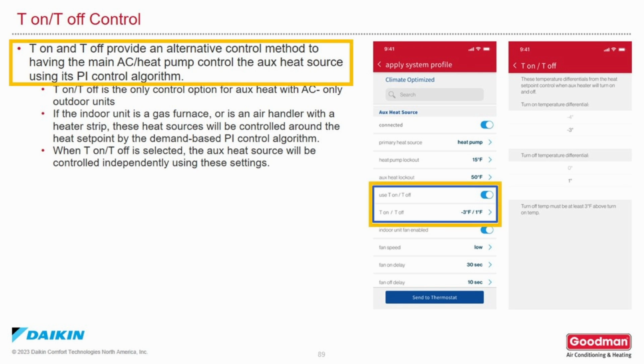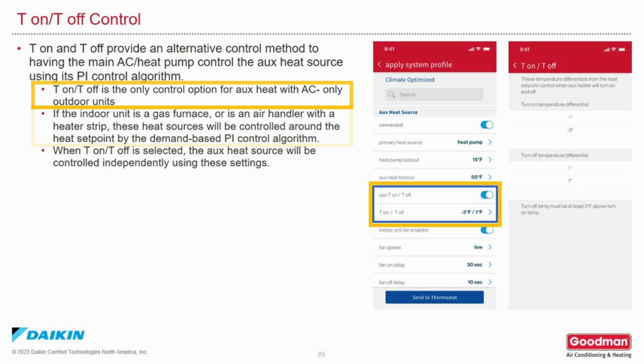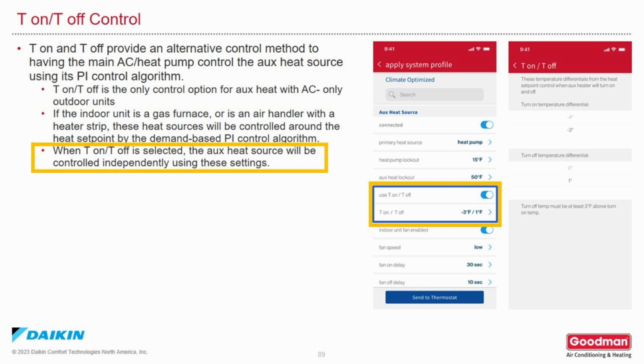T-on and T-off give you an alternative control method to having the main AC or heat pump control the auxiliary heat source using PI control algorithm. T-on and T-off is the only control option for auxiliary heat with cooling-only units. If the indoor unit is a gas furnace or an air handler with a heat strip, these heat sources can be controlled around the heat set point by the demand-based PI control algorithm. When T-on, T-off is selected, the auxiliary heat source will be controlled independently using these settings.